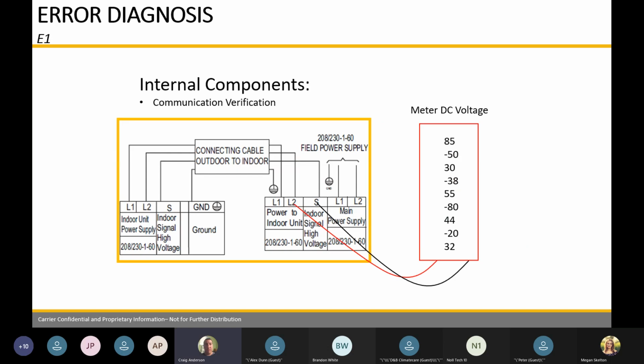So like I said, L1, L2, and S. L1, L2 is power coming in when we're checking our 220 volts. If we're checking our communication between our indoor unit, we're checking it between L2 and S. This is our signal. This is where we want to see outdoor unit is talking to indoor unit.